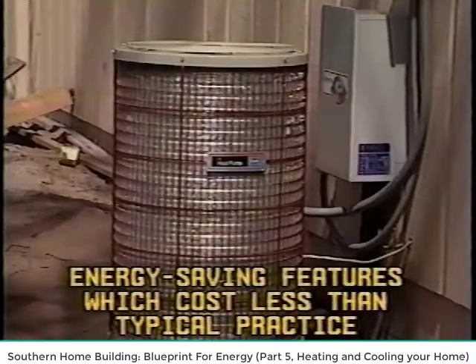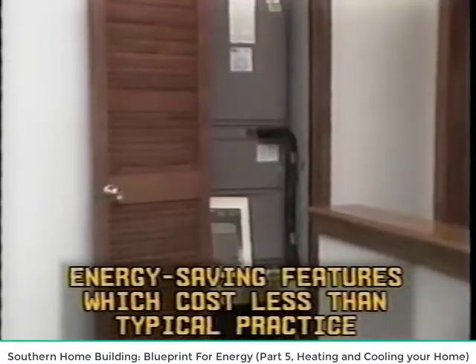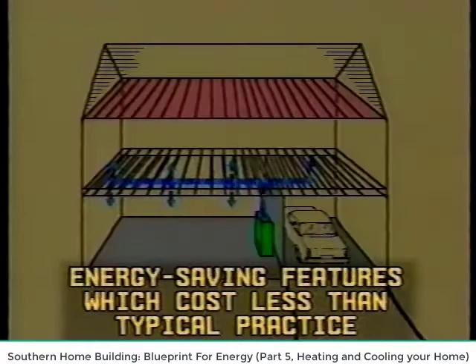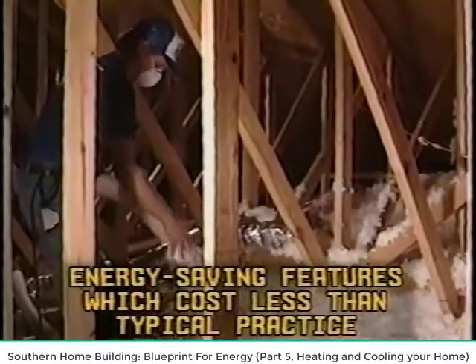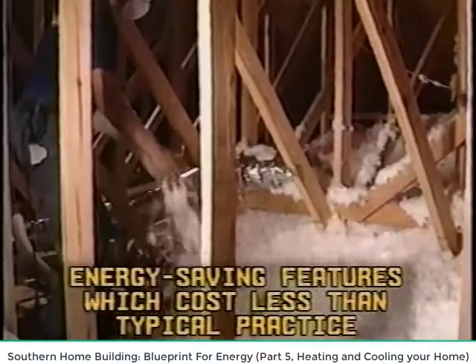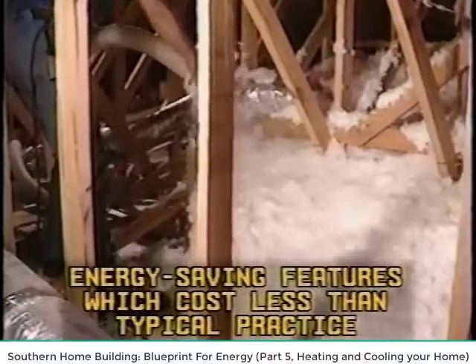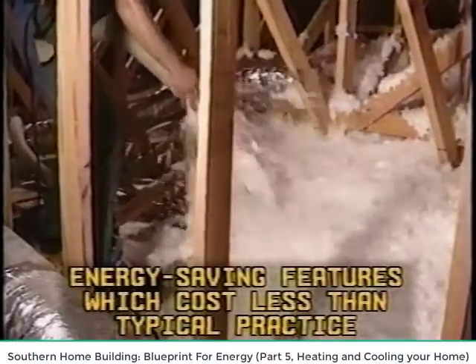Number 2, avoid using more than one heat pump, even in homes with more than one story. Number 3, use a free air return system. Remember to set aside a closet inside the house for the heat pump's air handler. For homes with more than one floor, locate as much duct as possible in the space between the floors. Number 4, use R30 blown-in insulation in attics whenever possible. It is less expensive than batts.